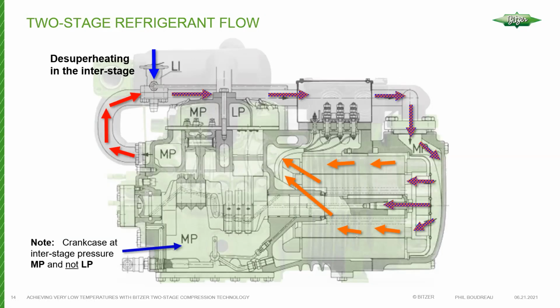Note also that the crankcase pressure in a two-stage compressor is at interstage pressure, not at suction pressure. Now, for those who use the suction line pressure as a reference for checking oil pressure, just to point out, that's the incorrect way of doing it.